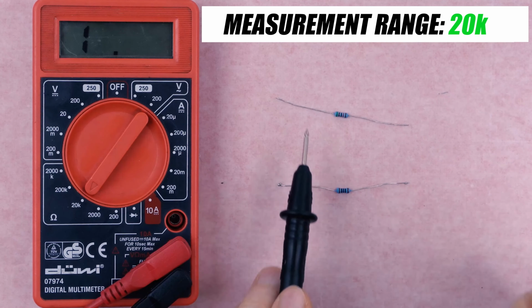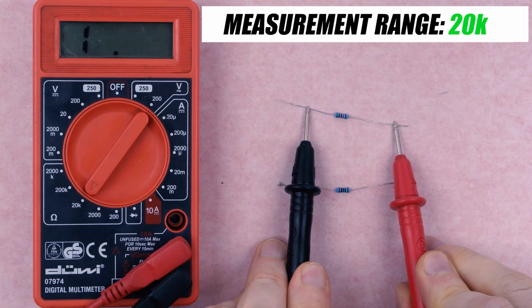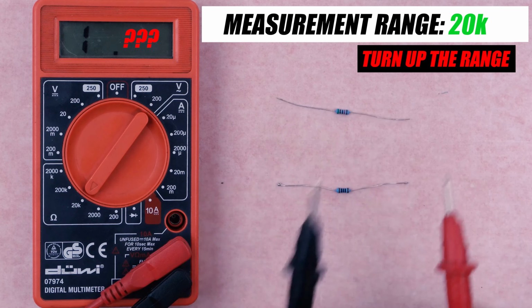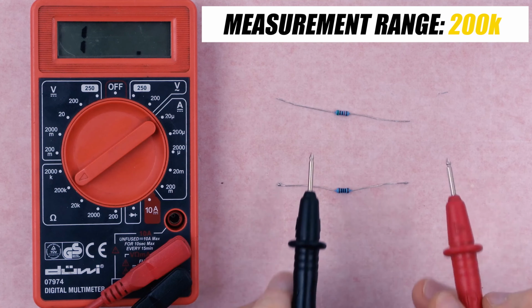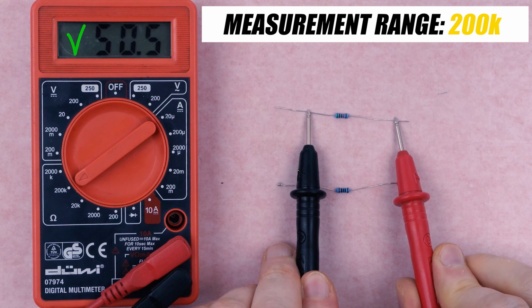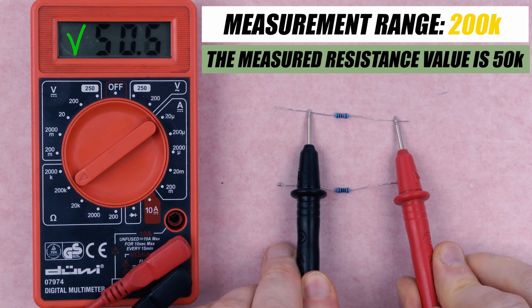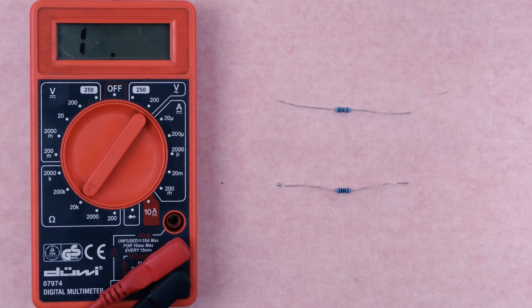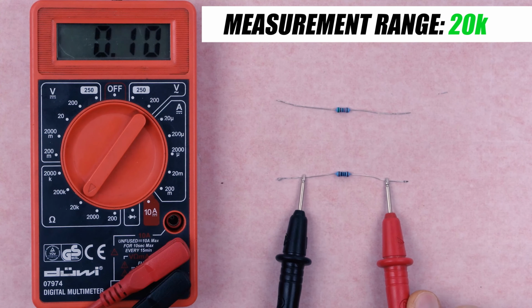If you need to measure a component whose resistance is unknown, it makes sense to start at the 20K setting. If you get the OL reading, open loop, no continuity, it means that the resistance is too high, and you need to set your DMM to a higher range. If the reading is near 0, it means the resistance is too low and you have to lower the range setting.